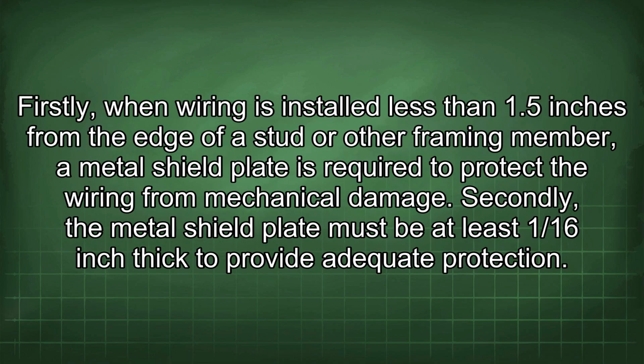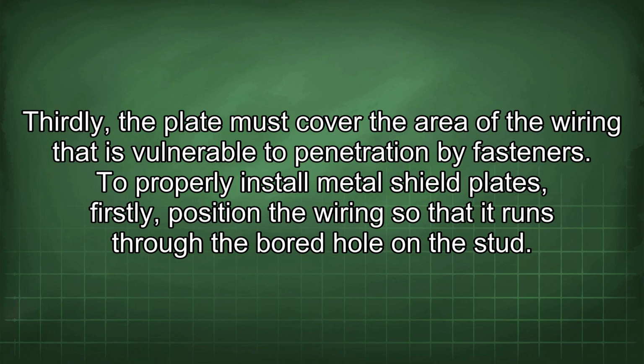Firstly, when wiring is installed less than 1.5 inches from the edge of a stud or other framing member, a metal shield plate is required to protect the wiring from mechanical damage. Secondly, the metal shield plate must be at least 1/16 inch thick to provide adequate protection. Thirdly, the plate must cover the area of the wiring that is vulnerable to penetration by fasteners.